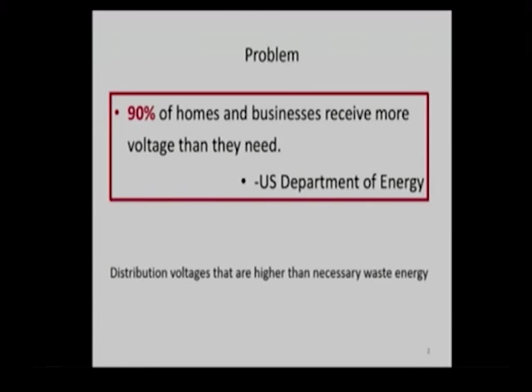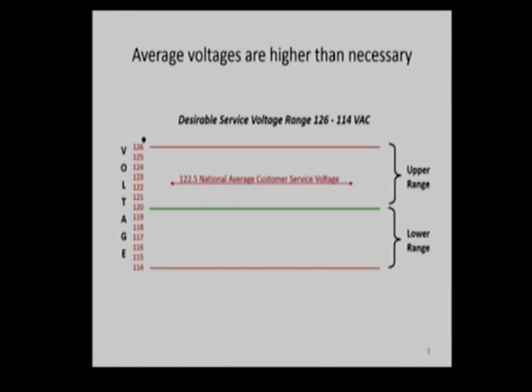About 90% of homes and businesses receive more voltage than they need. This is a survey from the Department of Energy. Distribution voltages that are higher than necessary really waste energy. The average voltage, if you put a voltmeter in a power outlet across the country, is about 122.5 volts. I've put here the desirable ranges for voltages coming from the electric outlet: an upper range from about 120 to 126, and a lower range from 120 down to 114. Historically, utilities have operated mostly in the upper range.